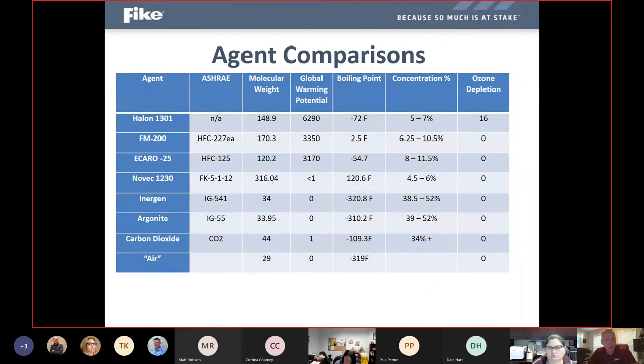standpoint, you can see that the biggest thing that ruled out Halon 1301 was up there in the top right, very heavy on the ozone depletion, where none of the other agents on there have that ozone depletion. The global warming potential was very high for Halon, but basically cut in half for the HFC products, being FM200 and Ecaro. But you can see where Novec 1230 is very low on the global warming potential scale. And that's why, especially as an FK or a fluoroketone product, it is not subject or target to any environmental regulations at this time, whereas the HFCs are going to be a little bit more reduced in their availability moving forward.